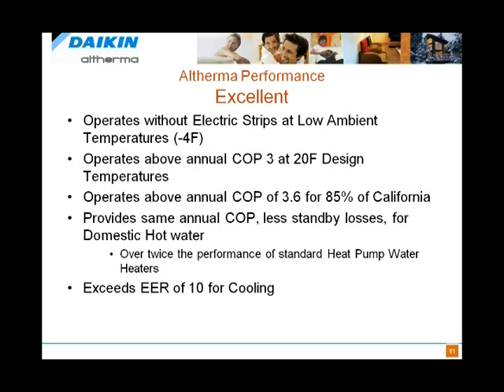Provides the same COP, less standby losses, for domestic hot water. So the domestic hot water is about twice what you'll see in terms of performance with this type of device compared to a standard heat pump water heater. And while we can go into the performance issues a little later, the EERs will be 10 for cooling or more on the smaller units.